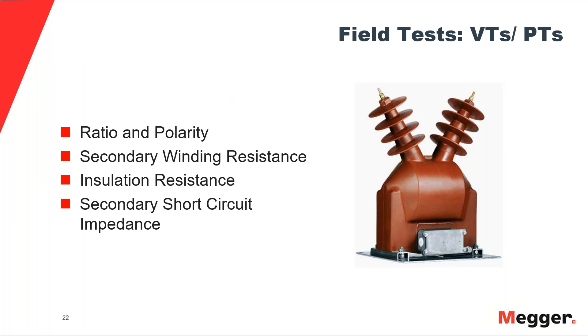That covers all the tests for CTs. Now let's move on to VTs — also called PTs or potential transformers in other parts of the world. We'll refer to them as VTs throughout the presentation. What tests can we do on VTs? Ratio and polarity, secondary winding resistance, insulation resistance, and the secondary short-circuit impedance.